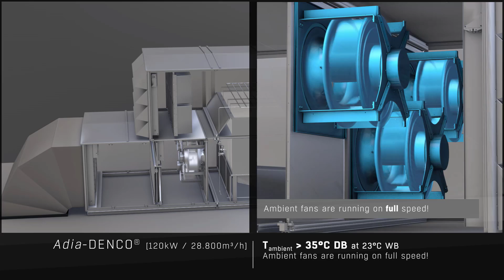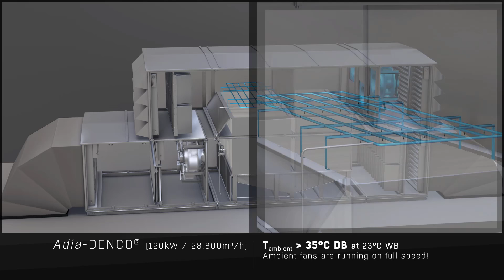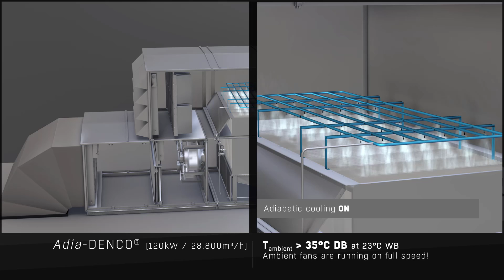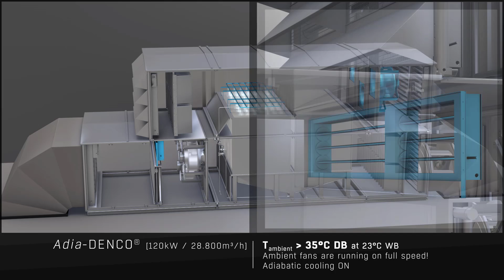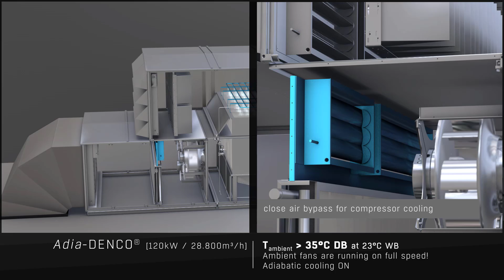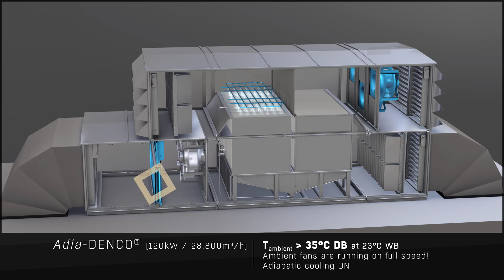The principle is that these units don't actually need any mechanical cooling - it's all done by evaporative cooling. These are used in hyperscale and large data centers where they've got some form of aisle containment, capturing either the hot or cold air, enabling us to use elevated temperatures onto these air handling units. Then the evaporative cooling process lowers that temperature and distributes it back into the room at the designated temperature we want.